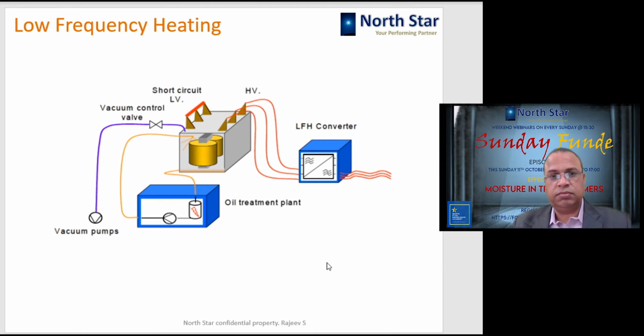This system basically has an oil treatment plant, where there is a heater and a pump which pumps the hot oil, and it gets sprayed on the winding. The oil is drained out of the tank, so there is no oil in the transformer tank; the only oil going inside is what is being sprayed. Then there is a low frequency heating converter which gives a very low frequency supply to the high voltage side of the transformer. Typically less than 10 hertz, or 5 hertz, frequency is capped, and high current is provided, so that the current going into the winding heats the windings up.